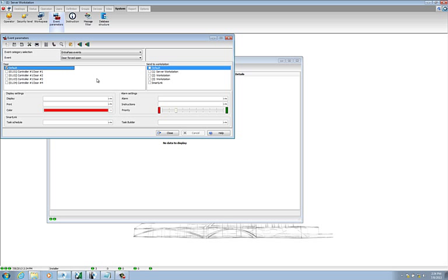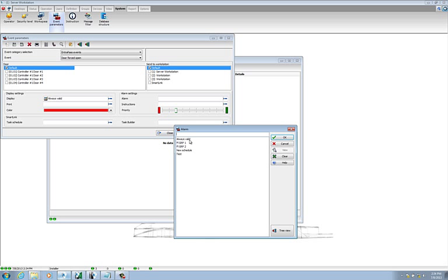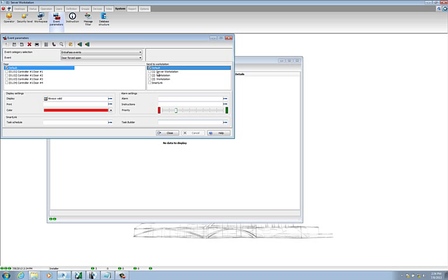If I select default and assign an alarm to that, it means there will be a pop-up on all the doors that have a door forced open, and it's going to display on all the workstations: the server workstation, workstation number 2, 3, and also the smart link. And even if you add other workstations afterwards, they will have a pop-up come up on the desktop also. So for the time being, we do not want to do that.